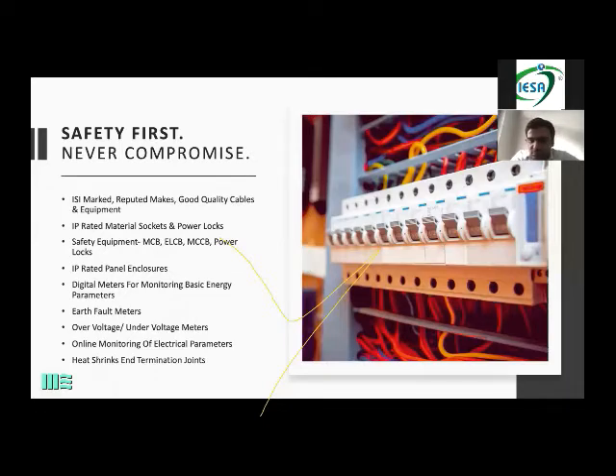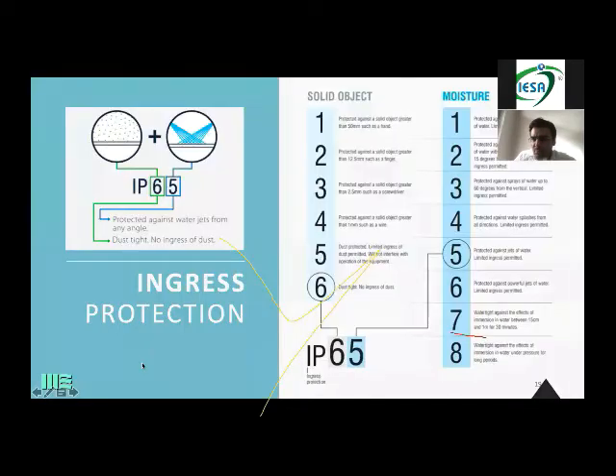If the house power has started or the genset has started, each and every hour we can monitor the energy, the load, the frequency. So we can do preventive maintenance of the panels. If something goes wrong, we get a signal that something is going wrong with the system. Rather than reaching a stage where something has gone wrong and we have no option, we can do preventive maintenance there and then. Heat shrink sleeves, again, we're going to talk about those.